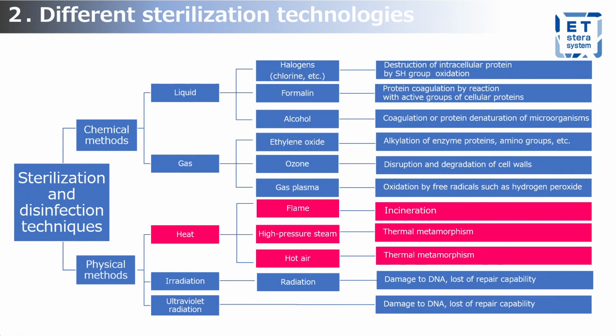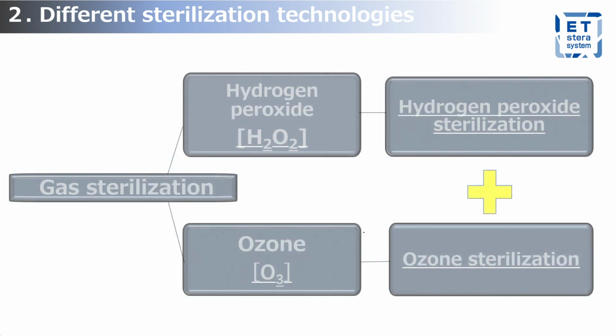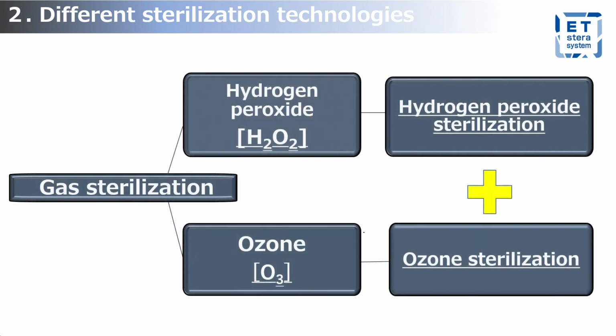As shown below, there are a range of techniques for sterilization and disinfection. ETstera, which we are showcasing today, is a form of hybrid processing that utilizes a combination of hydrogen peroxide gas and ozone gas. This sterilization method is to inactivate endotoxins at temperatures of 60 degrees Celsius or lower, which can be considered low temperature for the sterilization method.